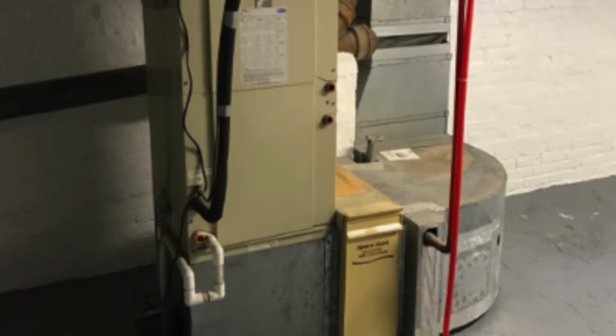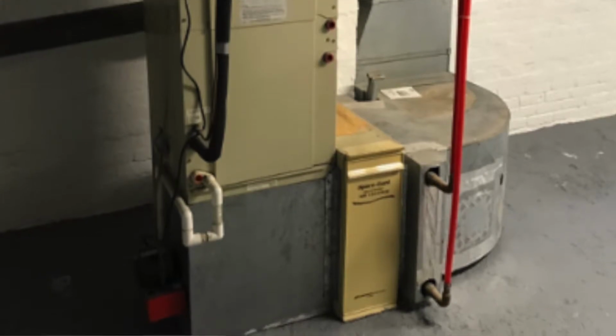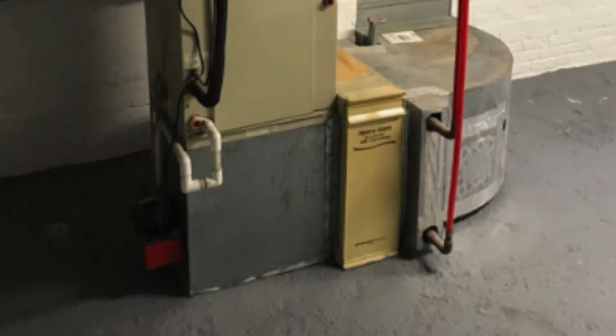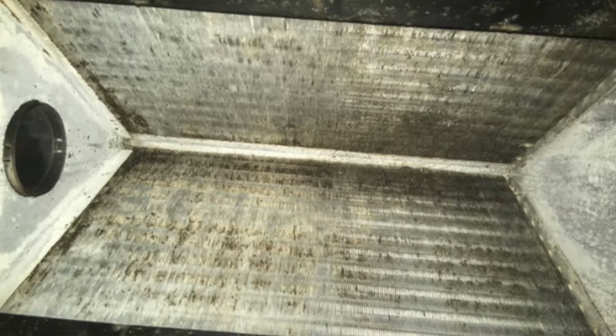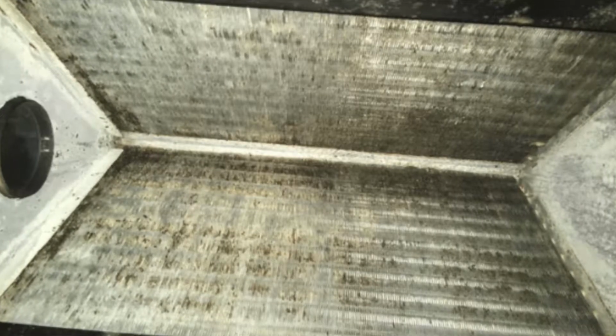It's really important that when you're looking at your HVAC system, if it's placed in a basement area, that the basement isn't dealing with any abnormal fungal ecology, and that the system is not placed directly on the slab floor. If you have an HVAC system placed directly on a slab floor in a sub-grade area, you're going to create a condensation differential between the bottom of the machine and the inside of the air handler unit. That gives excess moisture to the HVAC and can allow it to grow mold. We always recommend that if you have to put it in the basement, lift it off the slab so it's not touching the floor directly.